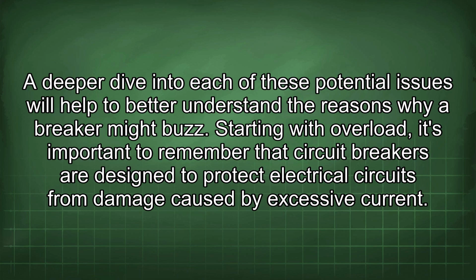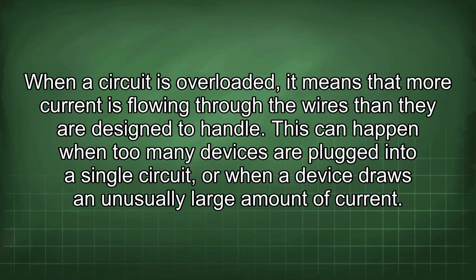breaker might buzz. Starting with overload, it's important to remember that circuit breakers are designed to protect electrical circuits from damage caused by excessive current. When a circuit is overloaded, it means that more current is flowing through the wires than they are designed to handle. This can happen when too many devices are plugged into a single circuit, or when a device draws an unusually large amount of current.